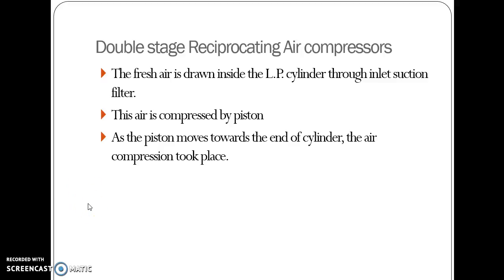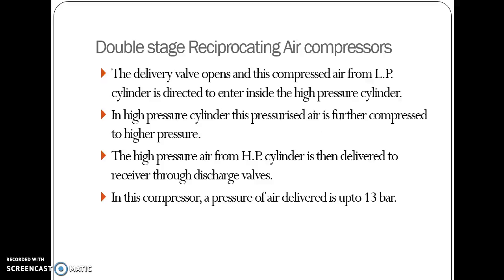The double stage reciprocating air compressor draws fresh air into the low pressure cylinder through an inlet suction filter. The air is compressed by the piston as it moves toward the top dead center. The delivery valve opens and this compressed air from the low pressure cylinder is directed into the high pressure cylinder, where it is further compressed to higher pressure. The higher pressure air is then delivered to the reservoir through discharge valves. This compressor delivers a pressure of up to 13 bar, compared to only 7 bar in a single stage reciprocating air compressor.